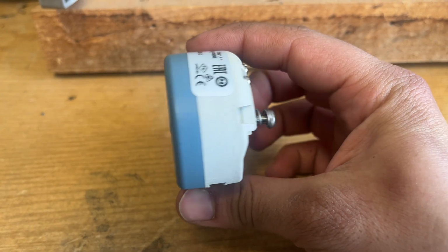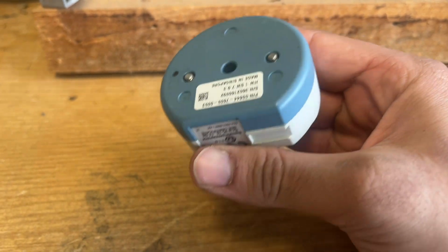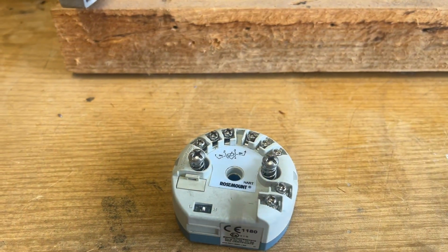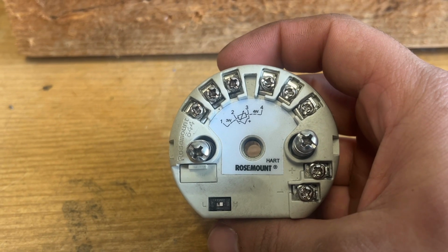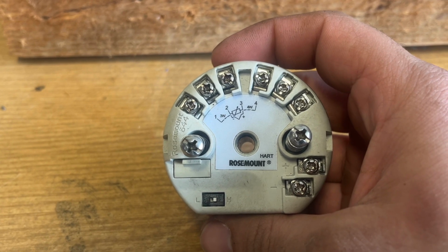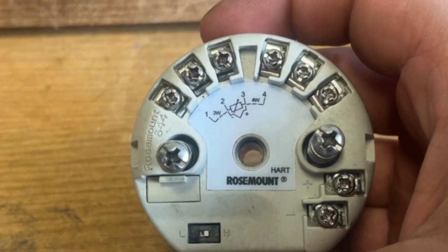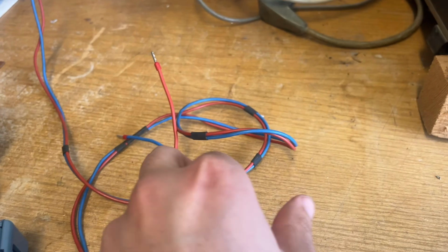Now, let's talk about the transmitter that will convert this resistance into a useful signal. This is a temperature transmitter. Its job is to convert the RTD's resistance into a 4 to 20 milliampere signal, which is commonly used in industrial automation. We have terminals for the RTD labeled 1, 2, and 3, and power input terminals plus and minus for 24 volts DC.